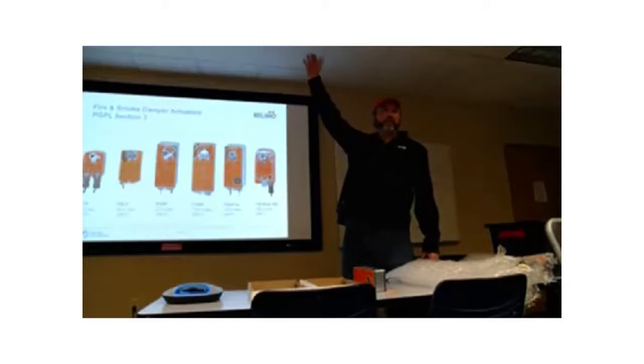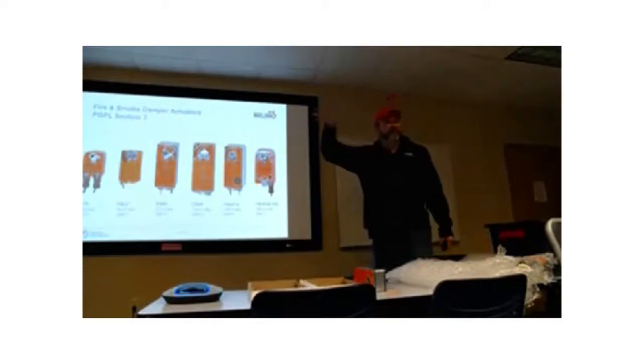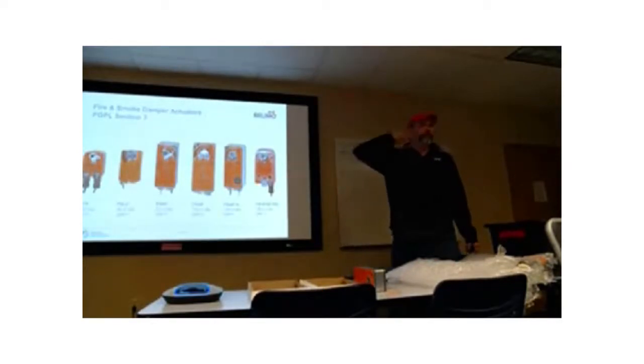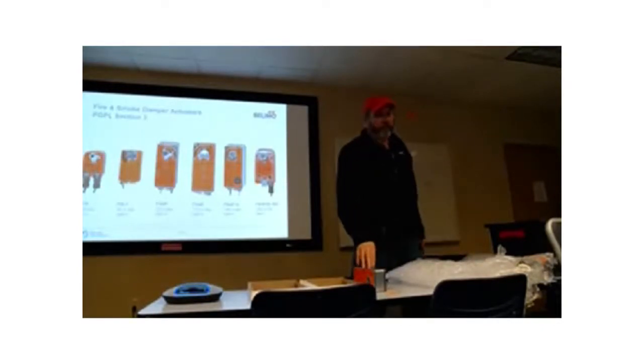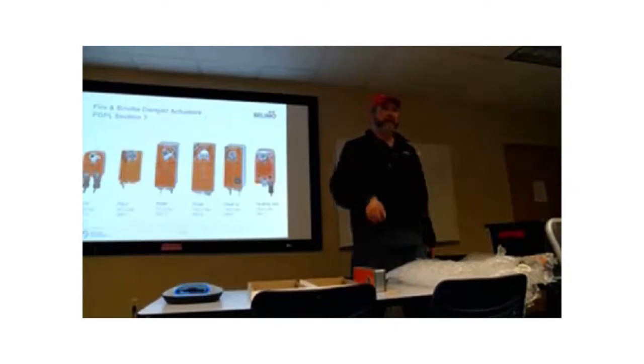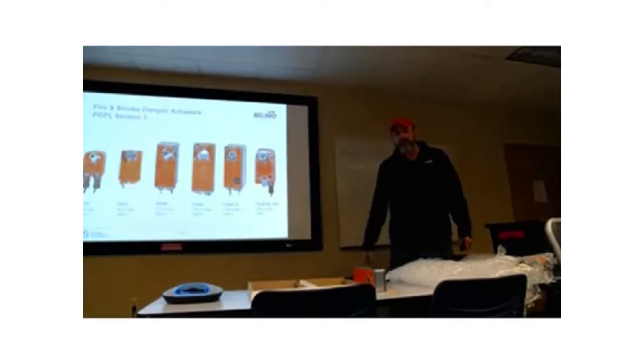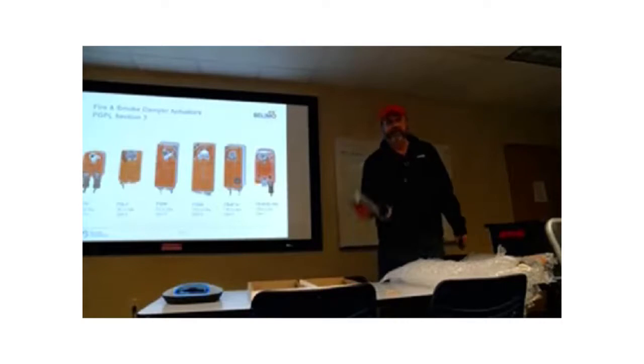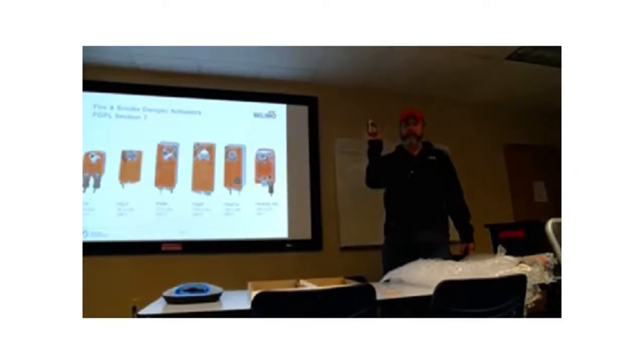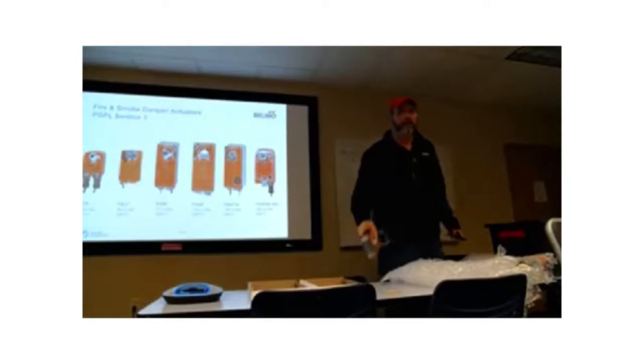Say you've got a multi-story building with reliefs on every floor, a relief damper on every floor that returns the air. You can control the relief air to that damper, to the air handling unit, and install it right in the shaft wall, in that rated damper. This can go right in that damper. It can actuate the fire smoke damper to control the relief air, and then when it becomes a fire smoke damper actuator, it's got to close, and it closes. So it's a dual purpose actuator, like you said.